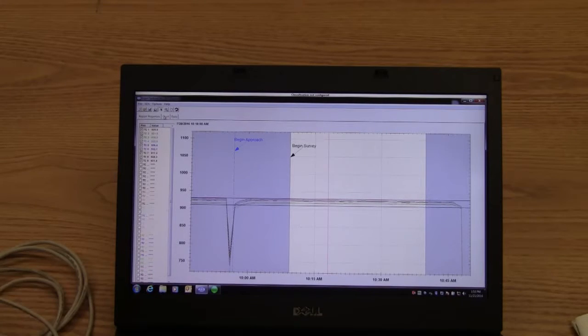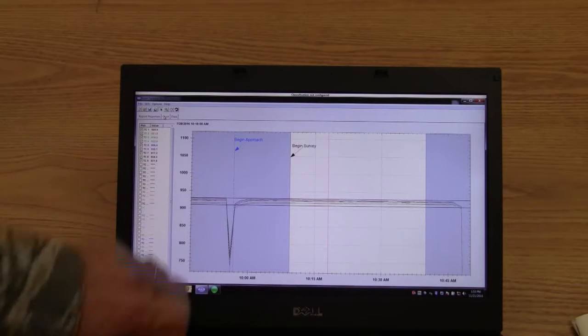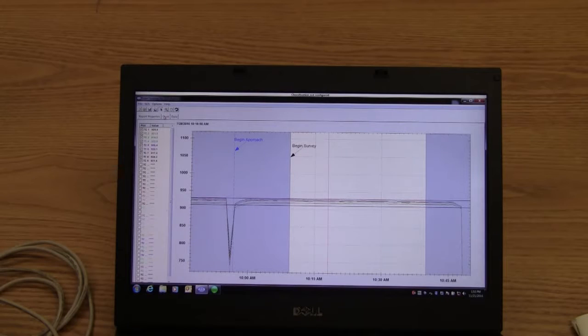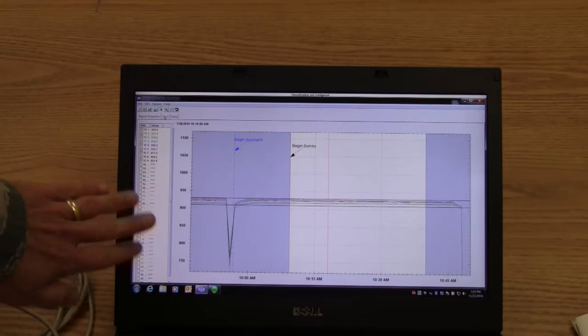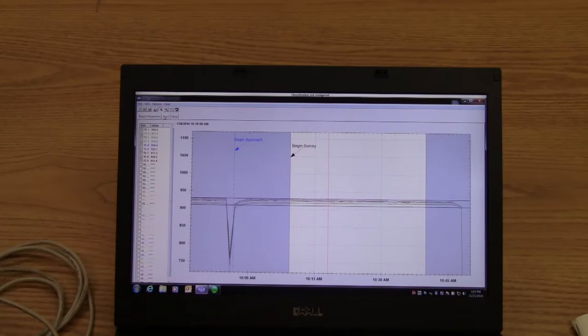or low spot on your graph, and it could actually dip above or below your line, but you wouldn't see it because your tolerance lines, as indicated by those 2 thick blue bars, are thicker than your TC indicator line, and so your tolerance lines could hide that deviation of 0.1 degree below or above your tolerance.